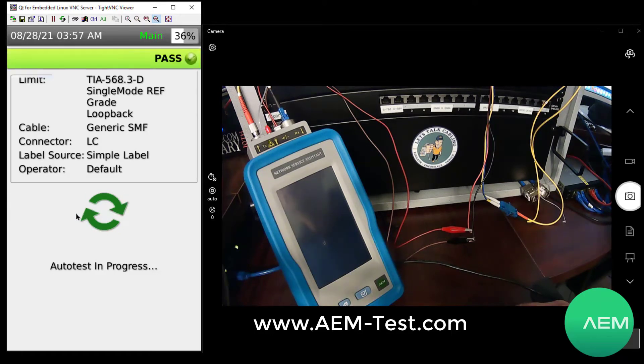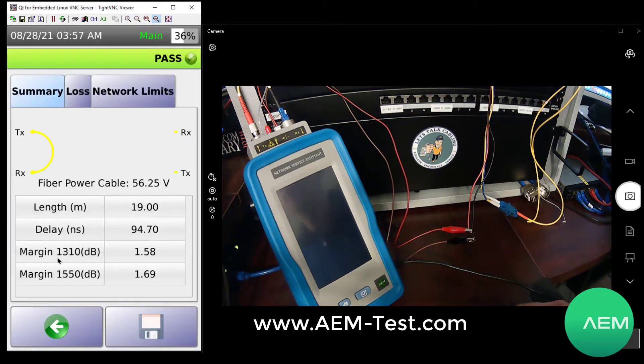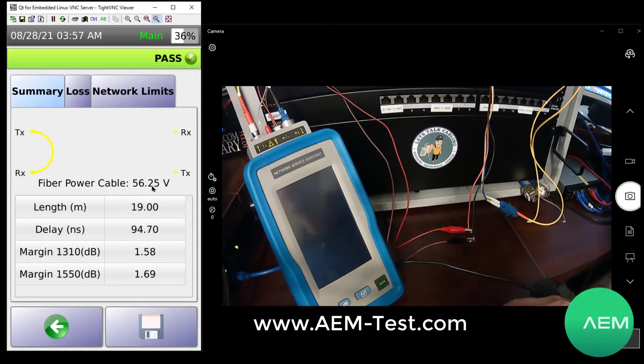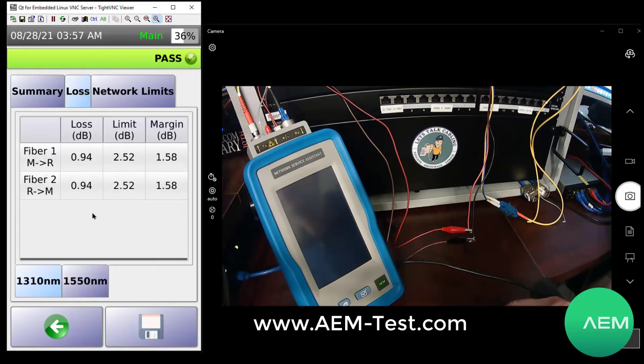In a short few seconds we have the test results. We can see that the power measured over that hybrid powered fiber is showing at 56.25 volts — this is PoE level power I'm running over this hybrid powered fiber. I can see the length of my fiber, the delay, and my margin at both wavelengths. I can go to my loss tab and observe the loss for 1310 nanometers, and also the loss for 1550, with margins for both as well.